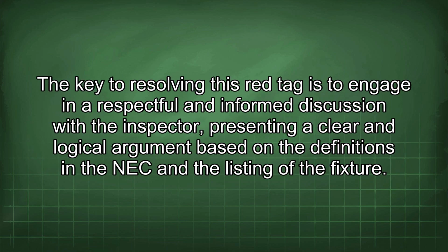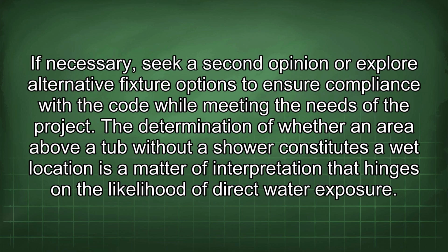The key to resolving this red tag is to engage in a respectful and informed discussion with the inspector, presenting a clear and logical argument based on the definitions in the NEC and the listing of the fixture. If necessary, seek a second opinion or explore alternative fixture options to ensure compliance with the code while meeting the needs of the project. The determination of whether an area above a tub without a shower constitutes a wet location is a matter of interpretation that hinges on the likelihood of direct water exposure.